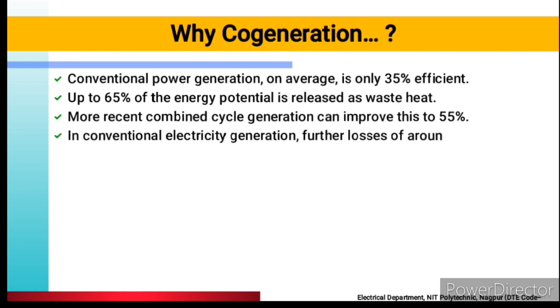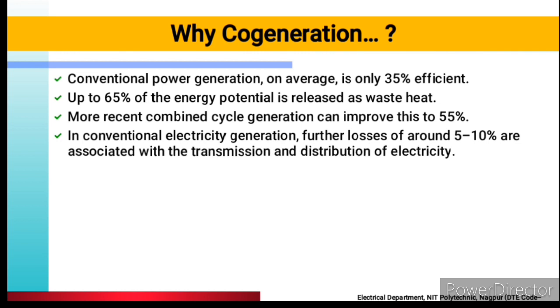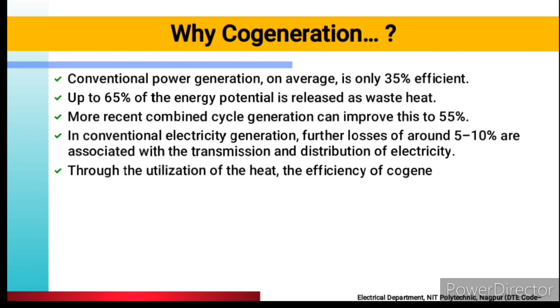In conventional electricity generation, there are further losses of around 5–10% associated with transmission and distribution. After 35% electricity is generated, we transmit it and then distribute it, and that also incurs 5–10% losses. So you are using 100% of fuel to generate electricity but you get only about 35% output. However, if we use co-generation, then the efficiency of the co-generation plant can reach 90% — you can get up to 90% energy.